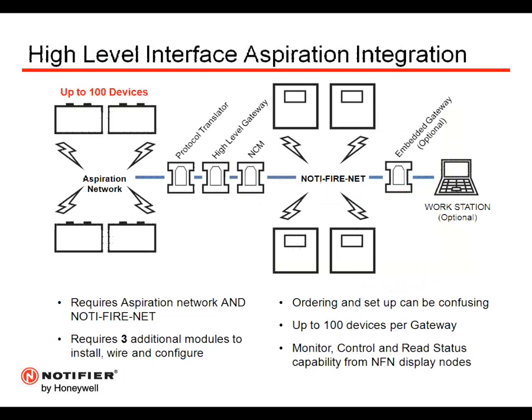We look at a high-level aspiration integration. It required an aspiration network. It required the same protocol translator to take the information from the aspiration network and make that available to the high-level gateway, which is also required. And then the high-level gateway connected to either an NCM or a high-speed NCM in high-speed NOTI-FIRE-NET applications to make that information available onto the NOTI-FIRE-NET network. So it required the aspiration network and NOTI-FIRE-NET.